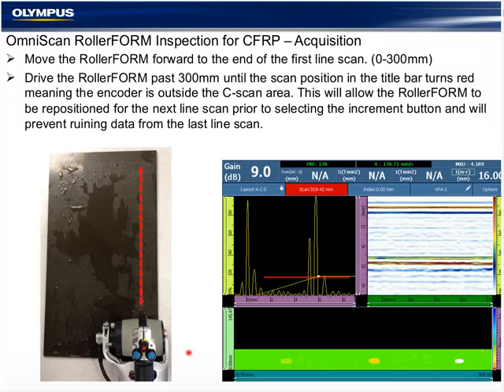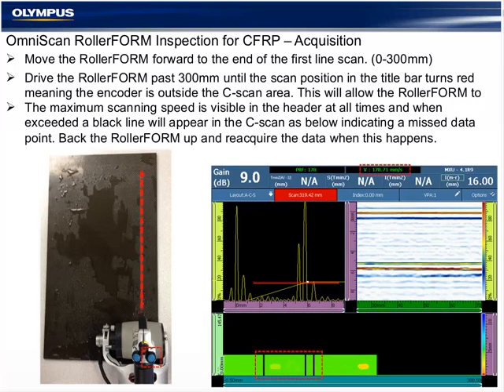I move all the way to the end of the first stroke, and I continue scanning so that my scan axis is outside the defined C-scan. Why I do that is because when I reposition the scanner for my second stroke here, if I'm outside the area of my C-scan, I won't contaminate any of the last data that I have right here. So I finish stroke 1, reposition to the second stroke.